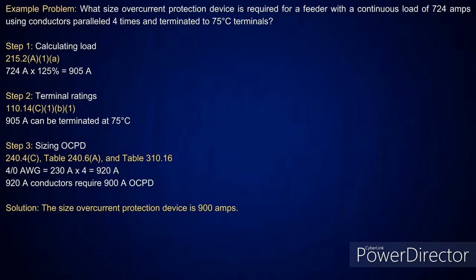Now, even when I'm sizing based on the overcurrent device, I'll still look at 215.3. It's got the same wording there for sizing for continuous. So the 905 amps can be terminated at 75 degrees C. Now, if I go look at Table 310.16, I need to get above that 905 amps. Okay. So if I'm paralleling it four times, the 4/0 is good for 230 amps. Parallel that four times gives you 920 amps, which is larger than the 905 amps of calculated load.